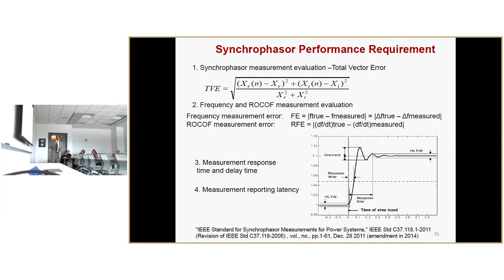Now, some of the performance requirements of the IEEE standard C37.118, which was revised in 2011 and brought in two parts. The first part described the performance requirements. Total vector error, which is the difference between the actual value and the measured value of the phasor, in most cases should not exceed 1%. It also defines frequency error, rate of change of frequency error, and the step response requirements in terms of how much delay is allowed, what the overshoot limit is, and what the response time is. So if you are developing an algorithm, you have to test it to meet these requirements.